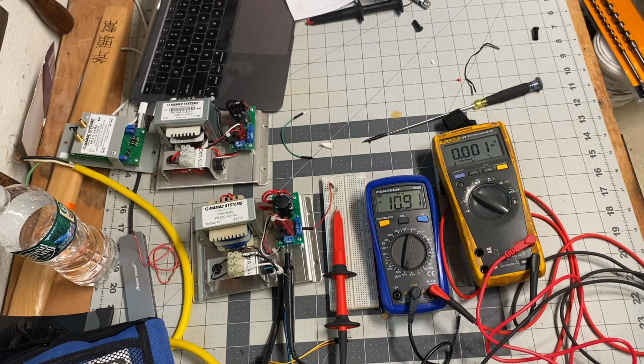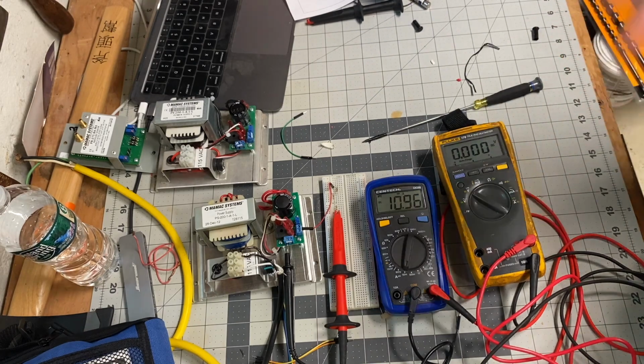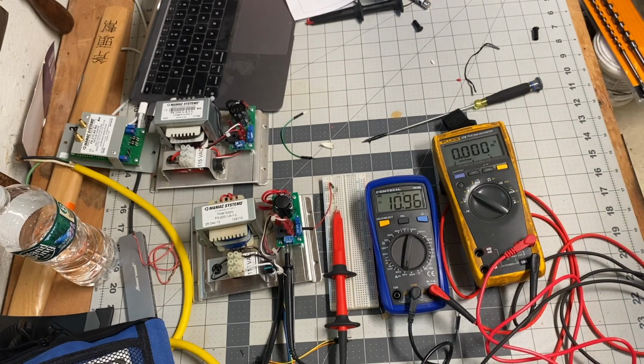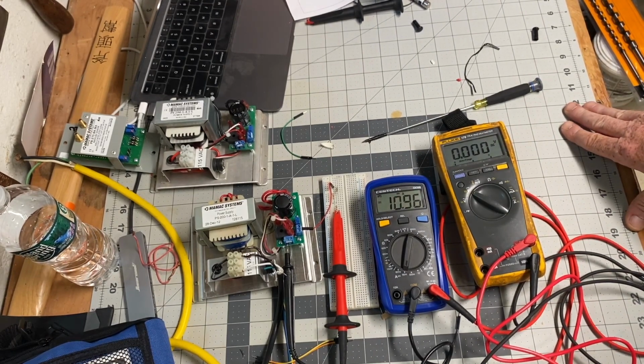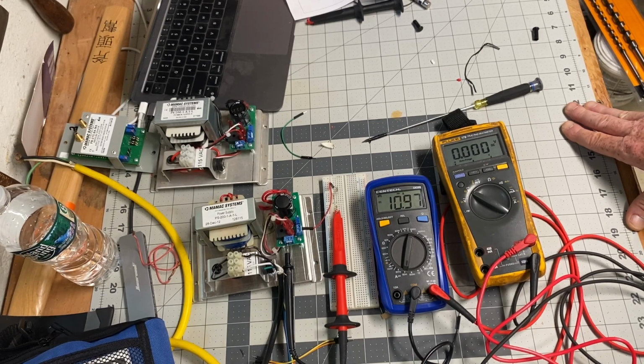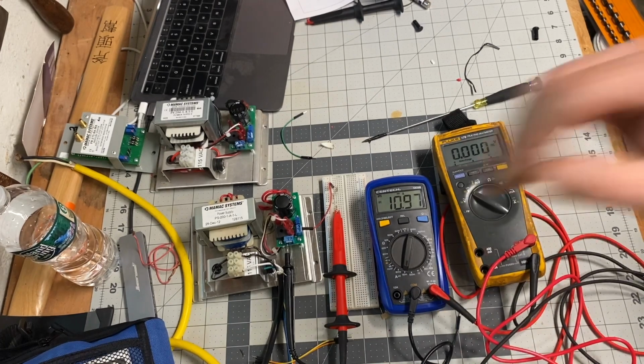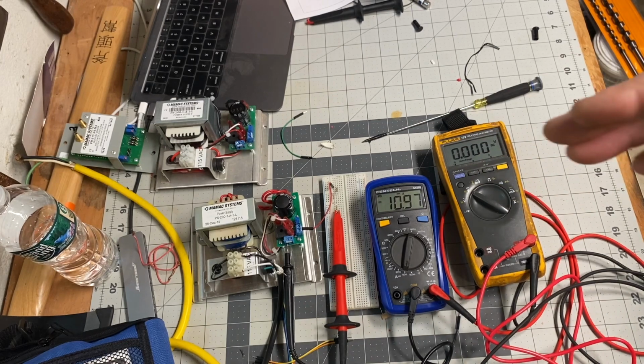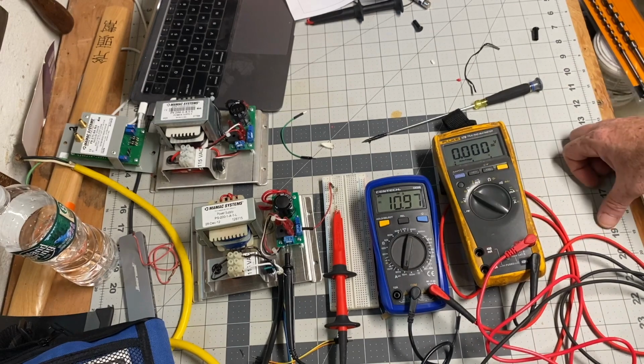We had the same problem with another transformer, same exact model, on a rooftop unit, and the static pressures, I think that transformer was putting out 17 volts DC. The static pressure sensors on the air handler basically weren't reading static, so they're feeding back like 4 milliamps. So the VFDs on the fans ramped up to full speed, so that air handler was maxed out for speed. Running at 60 hertz. I think it was a fan wall, so it might have been running at a higher hertz than that. And when we went up to that air handler and measured the static at the unit, we were measuring about 4 inches of static. Building was well over the 2 inches that the building was set for. So a bad transformer can give you really bad erroneous readings into your BMS system and just drive equipment crazy.